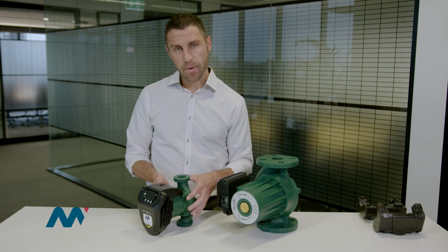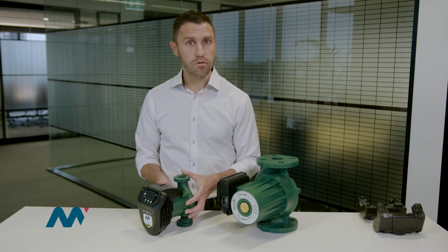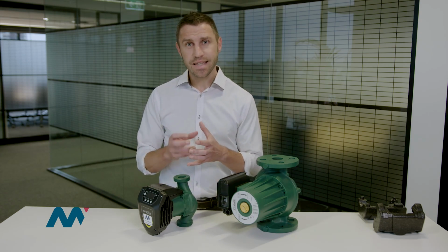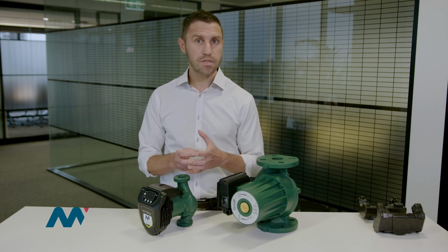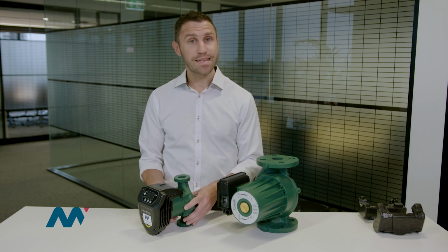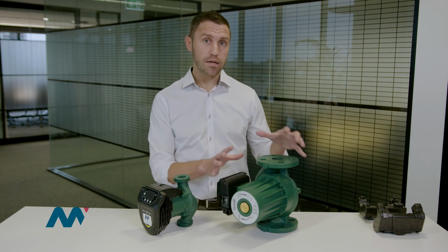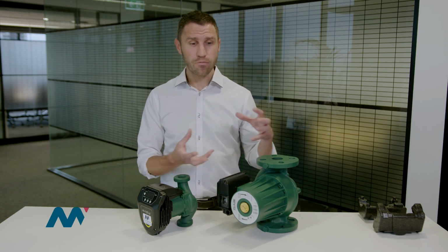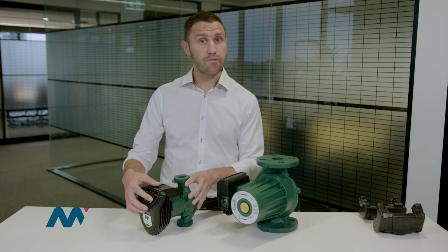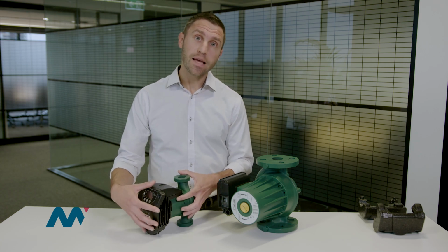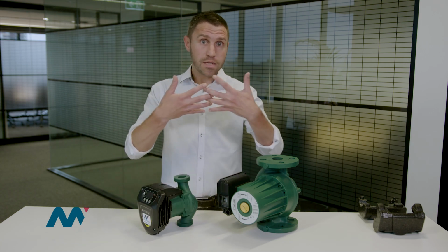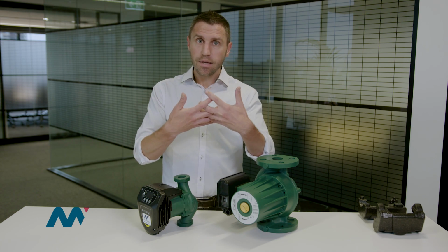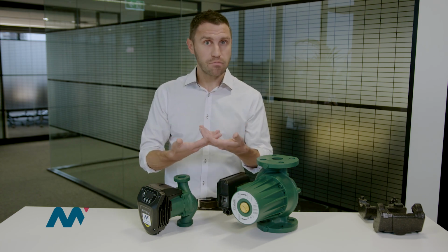The only drawback of the synchronous motor is that it needs the VFD, the variable frequency drive, an inverter, to start, because the torque that is demanded to start is higher compared to a normal motor. So you cannot operate this more advanced, more sophisticated motor with a normal switch. You need a VFD. That's why VFD and permanent magnetic motor always go together. They stick together because they need each other to have the maximum performance.